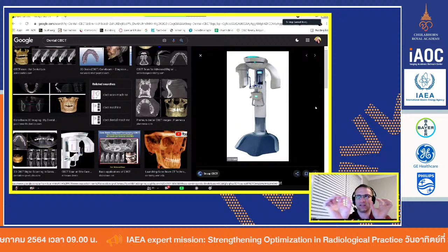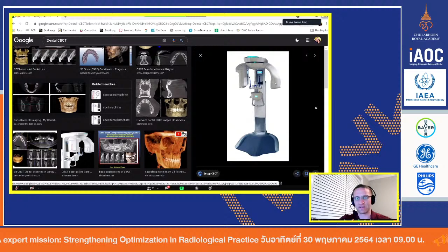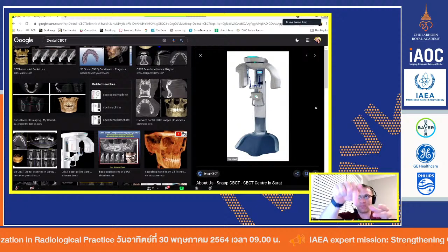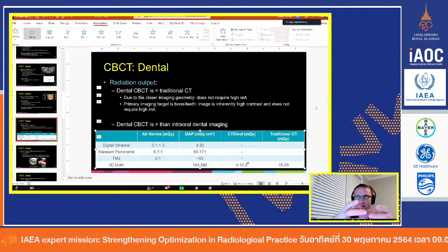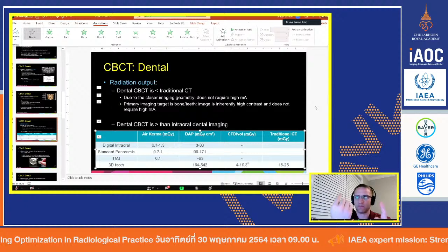If you put it in a real traditional CT scanner, because it can go all the way around, the left and right numbers are almost always the same. So when you do the CTDI calculations in these machines, you have to be very careful how you set up the phantom and where you put your ion chamber to make all your measurements. That said, it's the same calculation. These numbers, this 4 and this 10, I actually physically measured using my phantom and my 100 millimeter, or 10 centimeter, ion chamber. I did the rotation, I did all my averages, and I still did the same calculations.